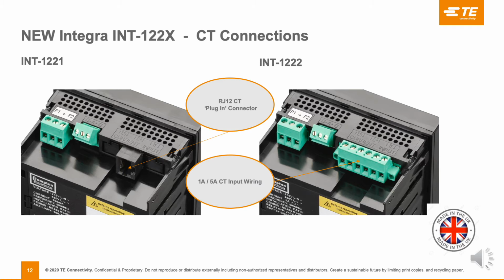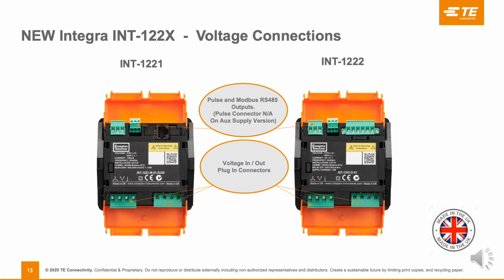And as you can see, to the left and to the right of the main plug, there are two screw terminals which connect it into the meter for safety, so the plug does not release, which obviously could cause high voltage there. So the safety side is accounted for. On the back of the meter, as you can see on there, we've done the top two connectors to the right hand side of each meter, which is the input one where we said the RJ12 and the 5 amp or 1 amp CT. If you look to the left of the input connectors, that's where you've got the Modbus and the pulse connectors on the top row. The Modbus is the center connector and the pulse is to the left hand side of the meters.